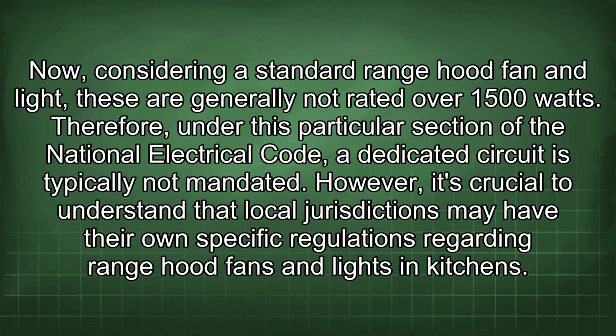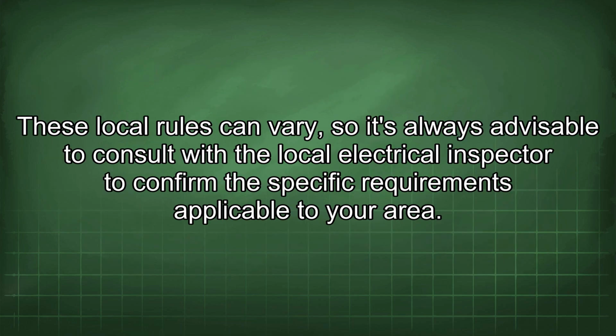Now, considering a standard range hood fan and light, these are generally not rated over 1500 watts. Therefore, under this particular section of the National Electrical Code, a dedicated circuit is typically not mandated. However, it's crucial to understand that local jurisdictions may have their own specific regulations regarding range hood fans and lights in kitchens. These local rules can vary, so it's always advisable to consult with the local electrical inspector to confirm the specific requirements applicable to your area.